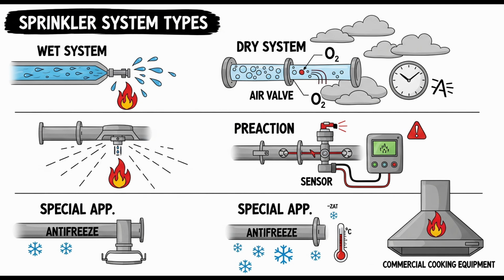It really suggests careful fine-tuning of these small details based on the specific application and the perceived risk or need in each case. It certainly seems that way. There is an exception provided for needing this check valve with a hole. It's not required if you're using specific types of dry pipe or pre-action valves that are listed for installation without needing any priming water, and they are designed to completely drain all water from above their seat after operation.